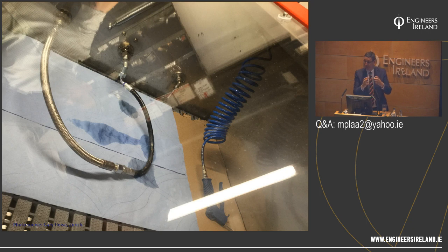But that's okay if you're dealing with air, but we're dealing with water. So the water had a route to roam by escaping from the pipework. So these were above the plasterboard ceiling. Now, we didn't do the design review on this. This system was installed before we got involved with it.